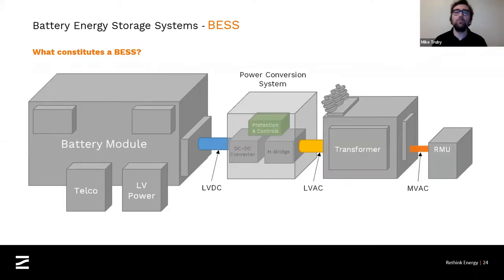What a BESS module typically will constitute is four main components, really, three or four components. So starting on the DC side of the system, we have the battery module itself. In a modern system, this is typically containerized. It might be in a shipping container style unit. We also see smaller units as well that stack together, DC coupled together in a modular fashion. This is essentially where all of our energy is stored, and we can call upon the batteries to charge or discharge real power in real time.